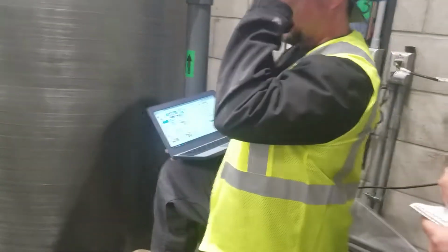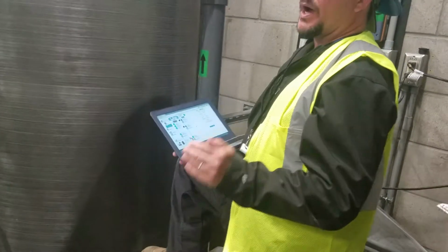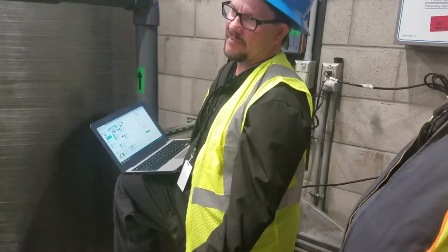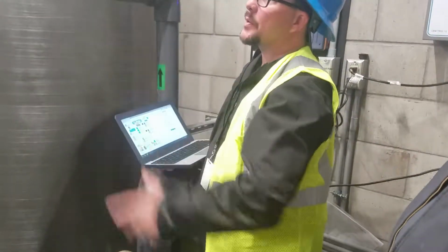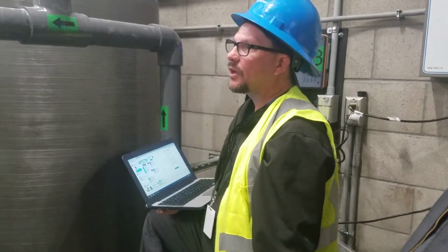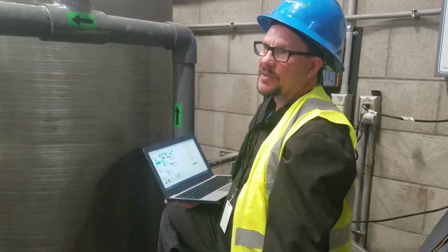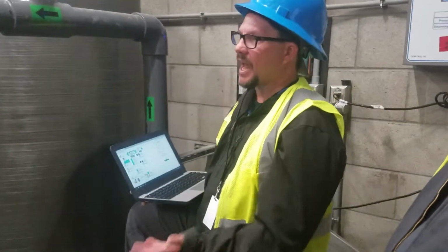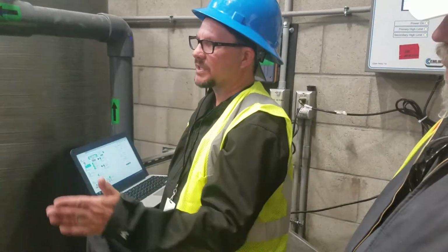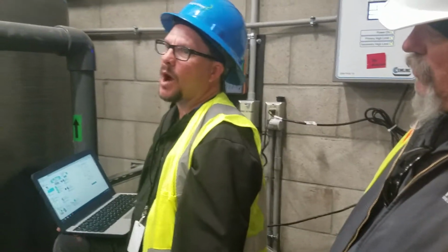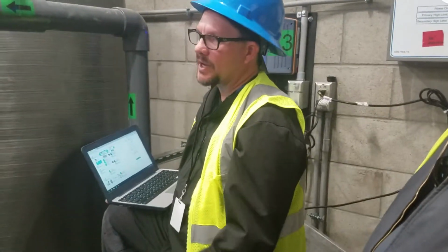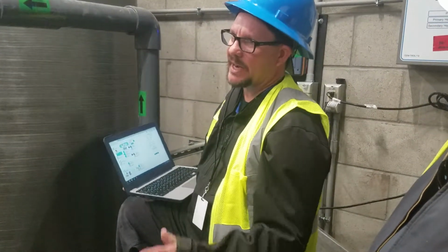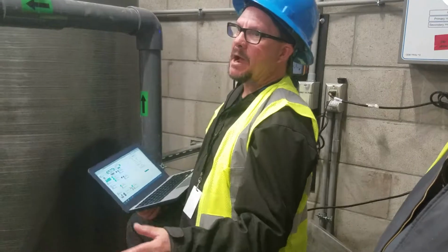Yeah, so what I can do, like I said, we don't know quite yet where we want the alarm parameters to be, how tight or how wide yet. We don't have a bather load. And then we know that we have a little bit of issues to work out with the CO2 on the feed times and things. So we'll do the best we can as far as setting up the controller with what we have, 0 bather load, and we'll get it to a safe set point. We kind of want to monitor them pretty closely until we get a really good handle on what's happening chemically, for obvious reasons. So we want to set the parameters fairly tight, but not so tight to where it's a constant nuisance.